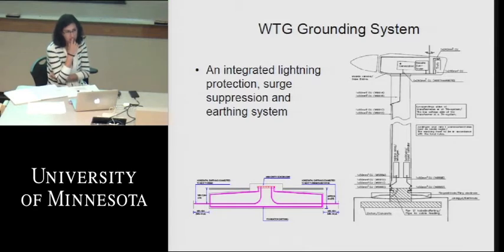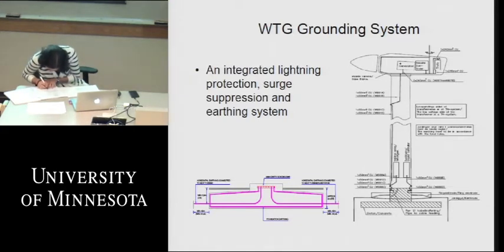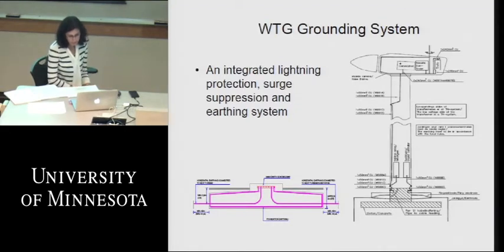And again, we use the tower as our primary grounding conductor from the ground point within the nacelle to where we actually inject the currents into the ground if we have a fault or a lightning strike. The system on the right around the foundation is kind of an older type of design, where we use a ring type of electrode with driven rods. You can see it's a kind of a ring that's around the circumference of the foundation, the hatched area there. And it's a full ring to accommodate 360 degrees around the wind turbine. And then we usually use driven rods to get down and inject those currents into the earth, so that they can be wicked away naturally. And people are safe and the equipment is safe from over voltages from faults and lightning strikes.